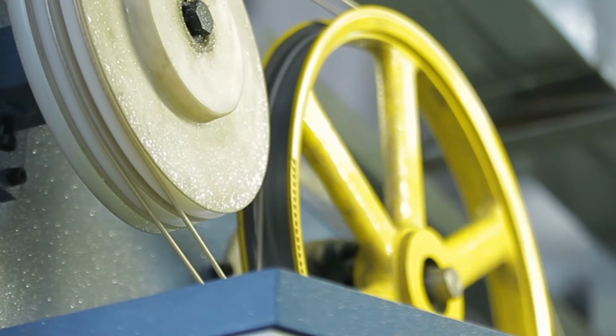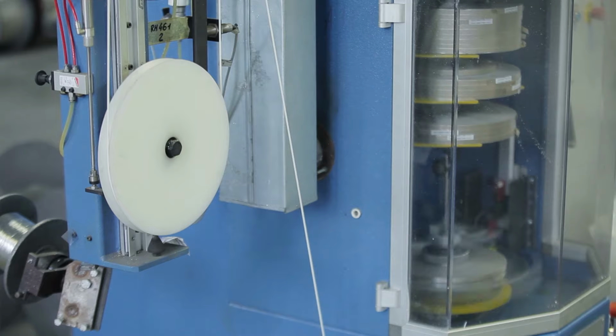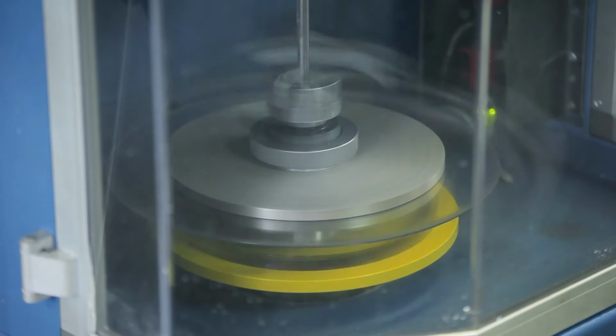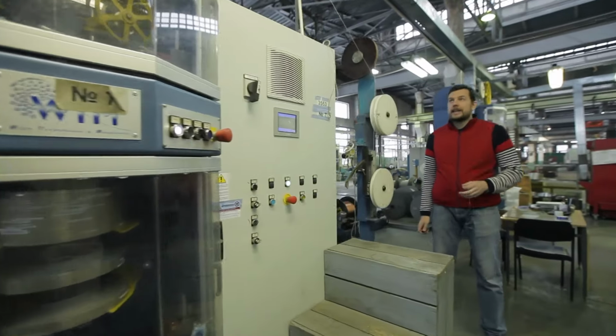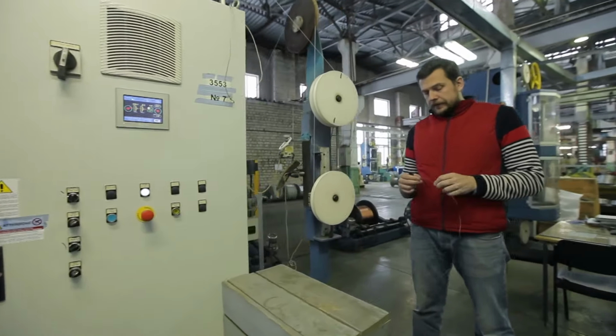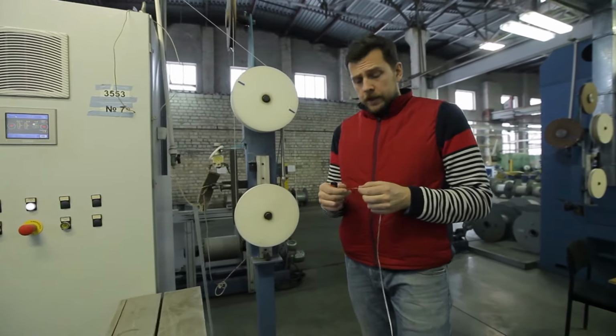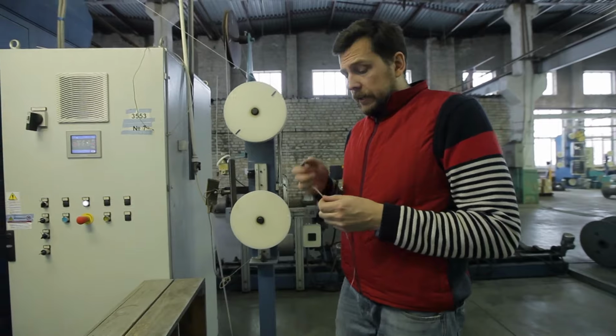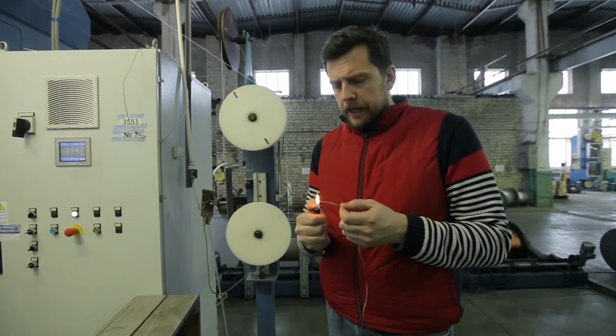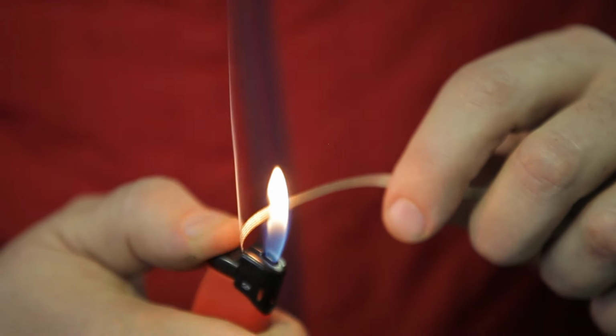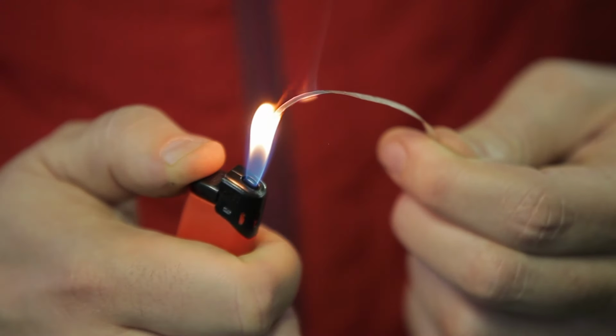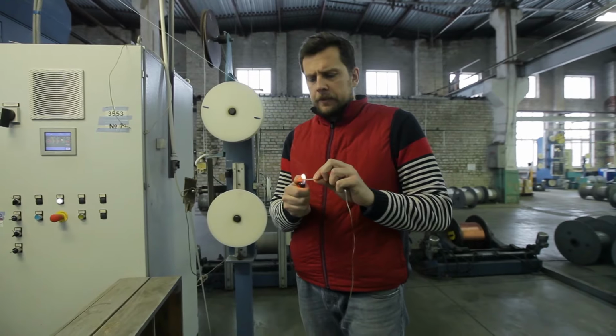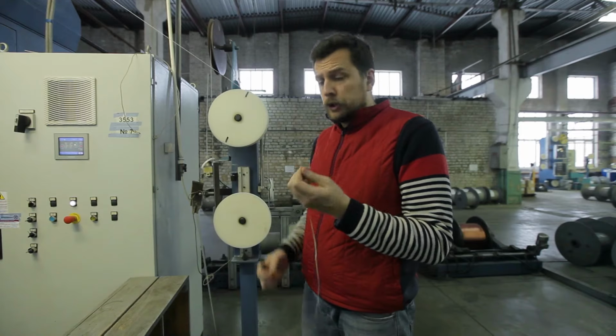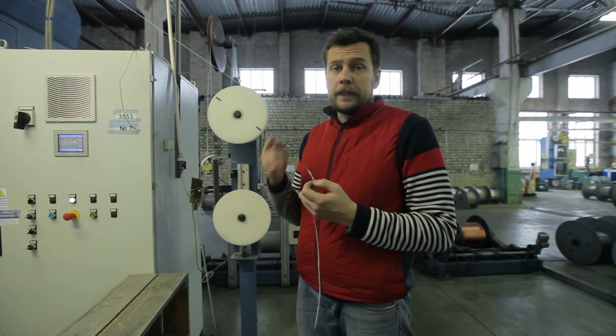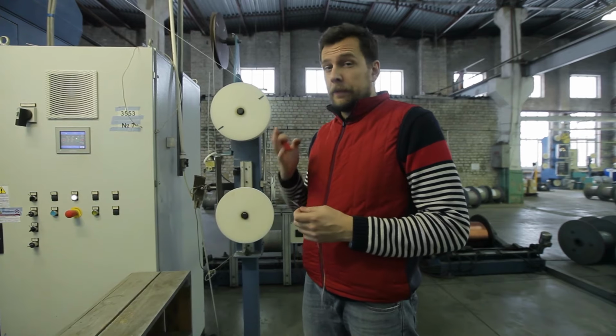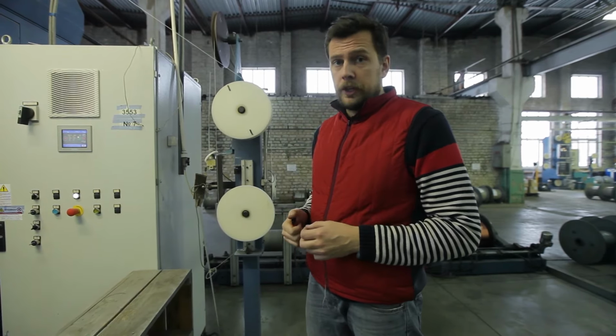There are specialized wires and cables. They are produced entirely with other machines and undergo even more stringent checks. On this machine, fire-resistant cables are braided. The metal is covered with this ribbon. This is fiberglass, which is covered with mica. And its most important task is not to burn in the open flame. We can do this for a very long time with a lighter, maybe even a soldering lamp, but this insulation won't lose its properties. Even our simple test shows that nothing has happened at all, although they are much harder tests than such cables undergo in certification centers.